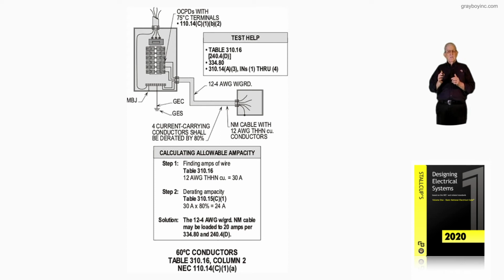But many engineers and designers and electricians routing conductors would look at the 10% rule. And you see from the panel board to the left to the equipment to the right, they would not route more than 10% of that run through a higher temperature than 86 degrees Fahrenheit without derating for correction factors. Now here we have adjustment factors because we have 4 current carrying conductors.